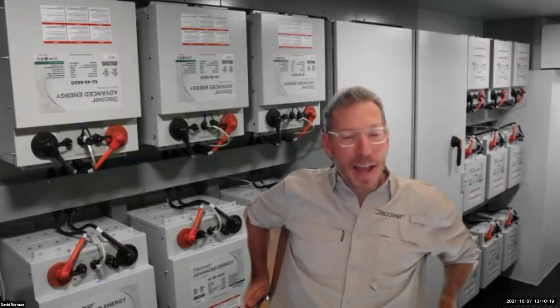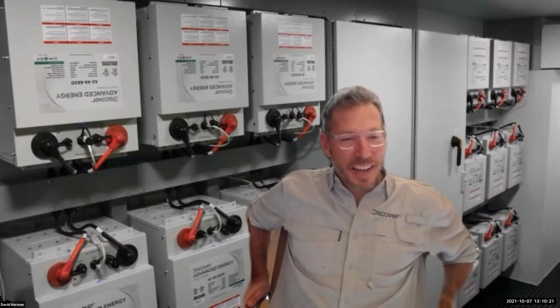Let's keep going. We have some more questions here. And just maybe this is a really quick one. What's the float voltage for open loop system, David? You mentioned it, I think. The float voltage at our battery terminals that we want to see is 53.6.